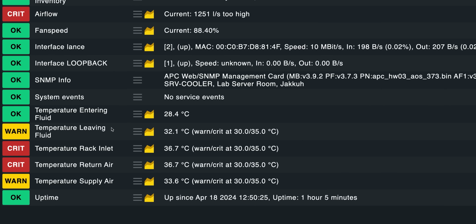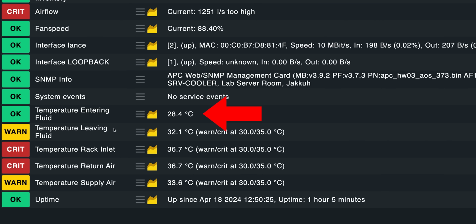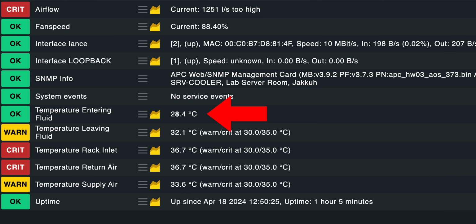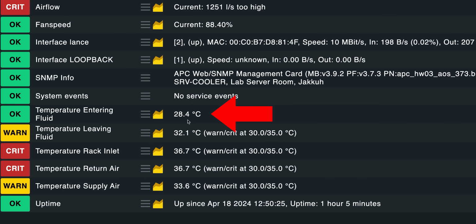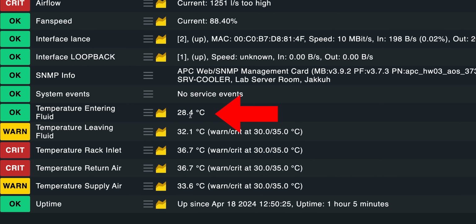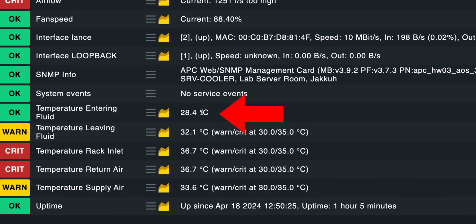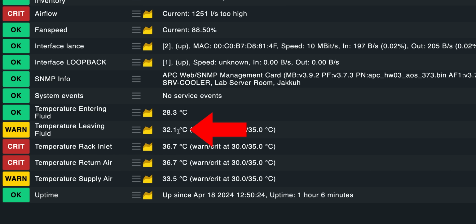This is a cool software called CheckMK. It's a monitoring tool that's open source, very awesome. We've hooked up the systems with SNMP, a monitoring protocol, and you can see the coolant coming in is 28 degrees from upstairs, coming from the warehouse, after it's been cooled with air that's around 21 degrees. Then leaving here, it's 32 degrees. That's a 4-degree difference, that's a lot of heat.